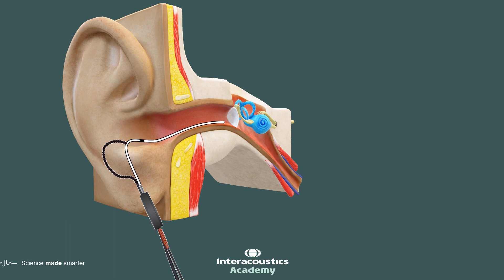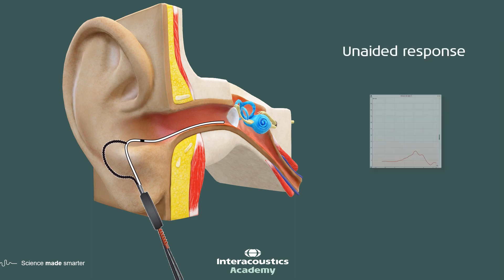So what is real ear measurement? Essentially what we're trying to find out is when we play a sound into the ear canal, what sound is being received at the eardrum? First of all, we do this in an unaided situation, where we place a probe microphone into the ear canal and then play a sound, and receive that sound at the eardrum. The probe microphone listens to that sound and graphically represents it as an unaided response.